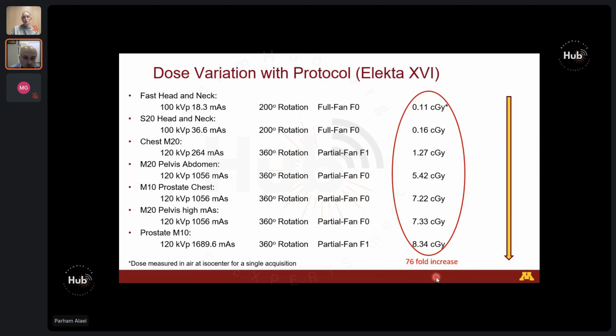And these doses were measured essentially with the Farmer-type ion chamber at the isocenter and then converted to dose. So this is not a patient dose. This is just a measure of the output of the unit in that condition. And as you can see, going from the lowest imaging dose to the highest is a 76-fold increase. So there's a substantial increase in the beam output, essentially, with a change of protocols.